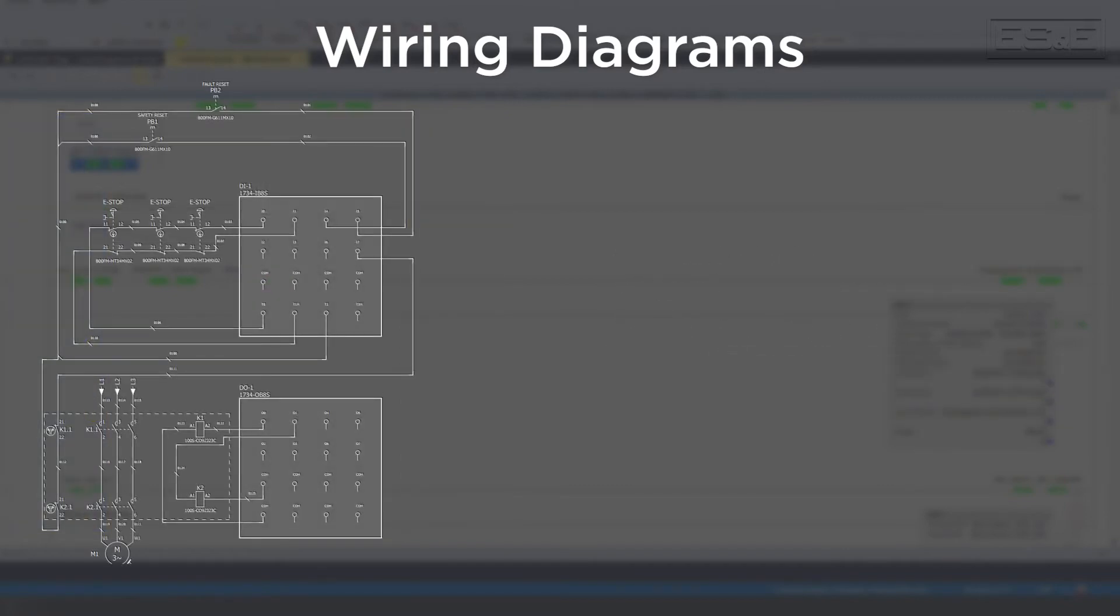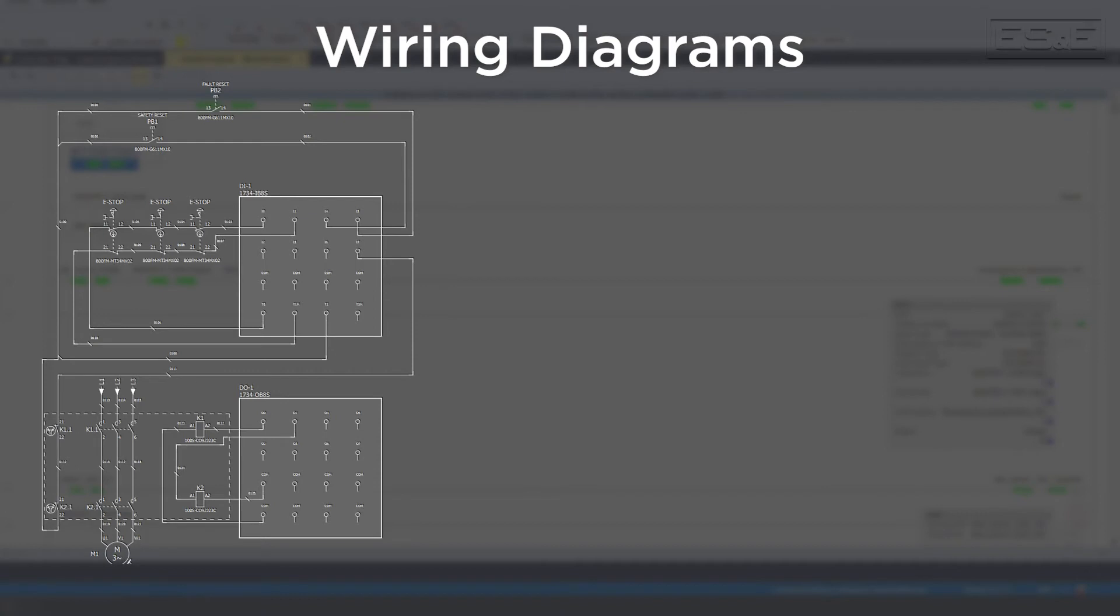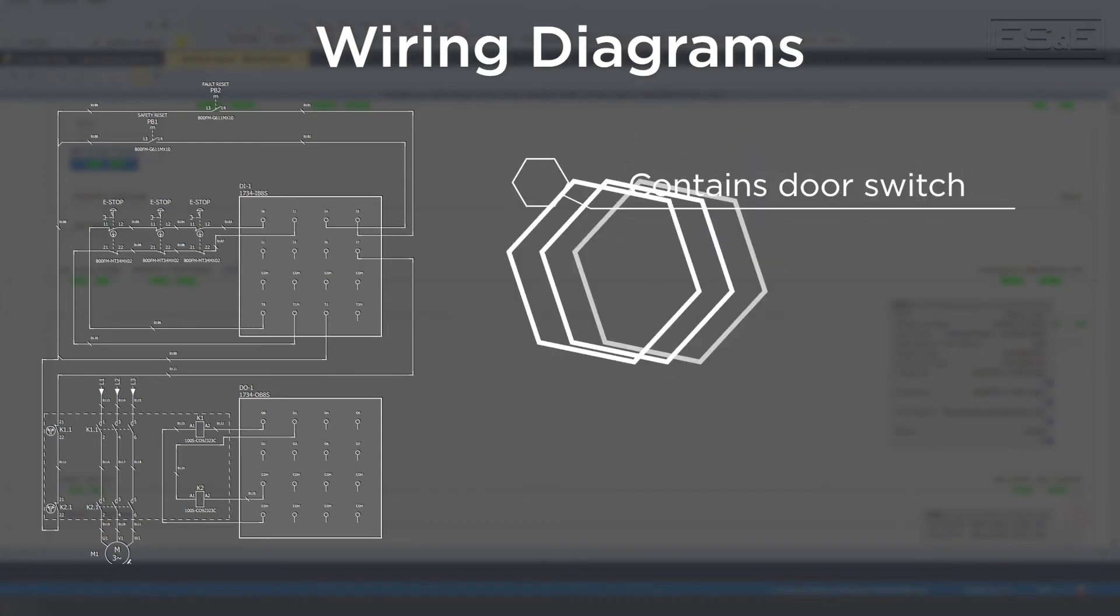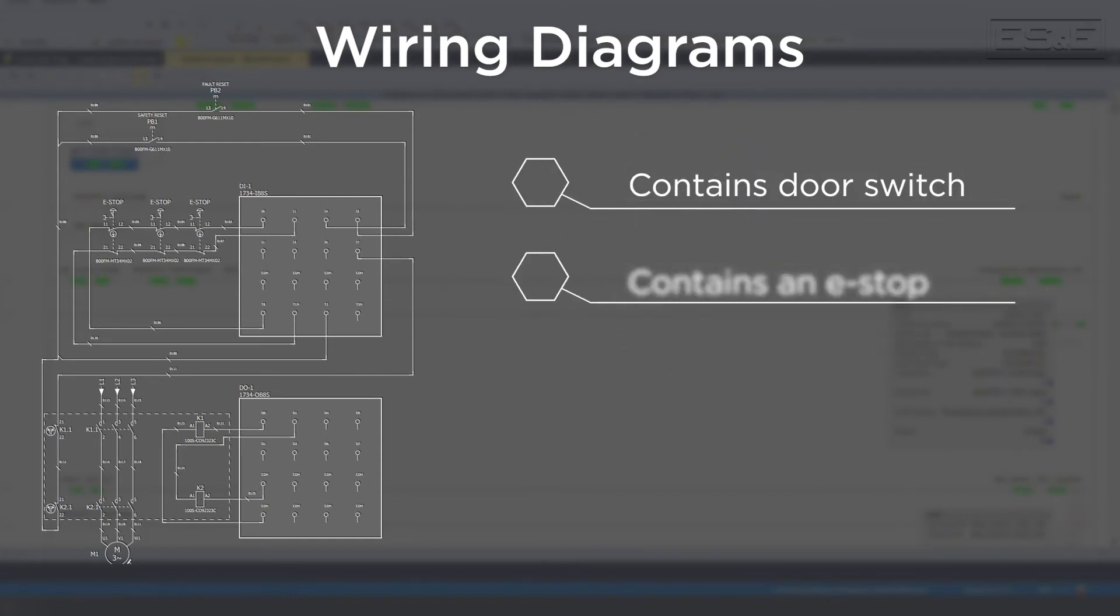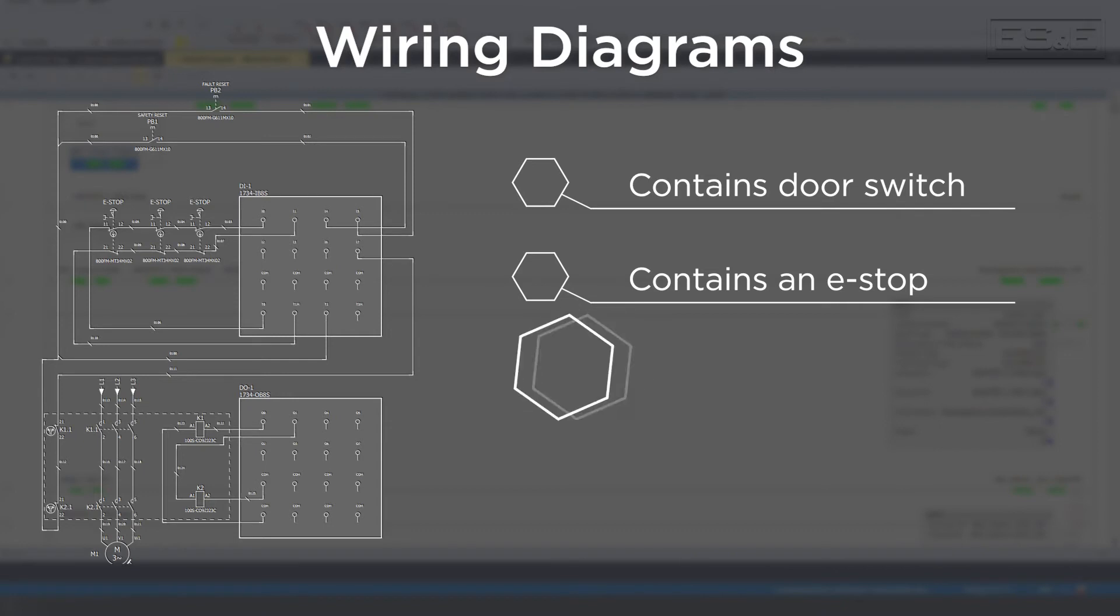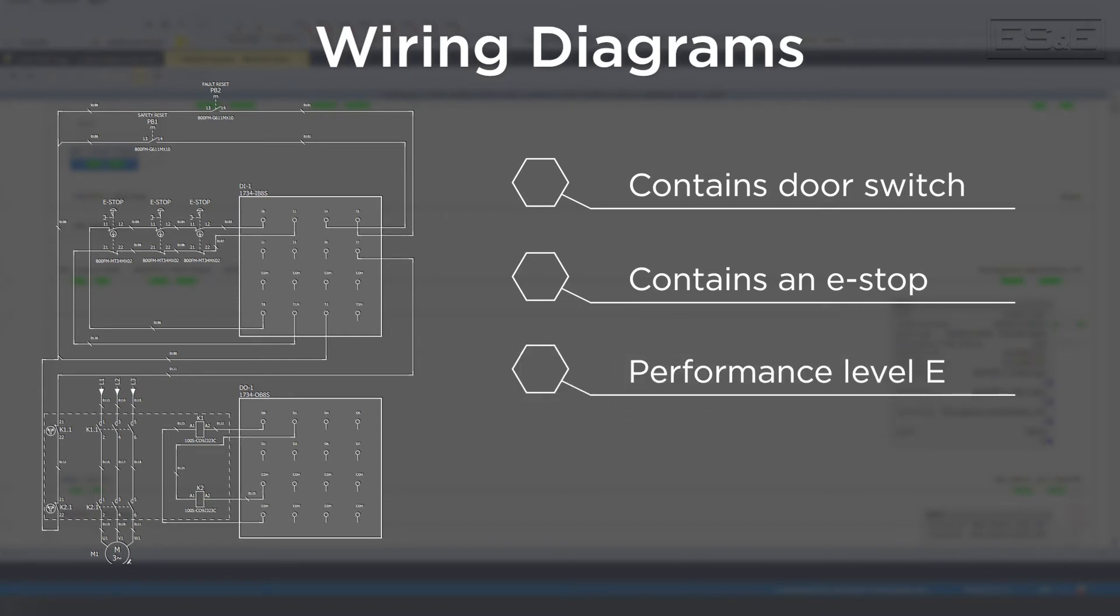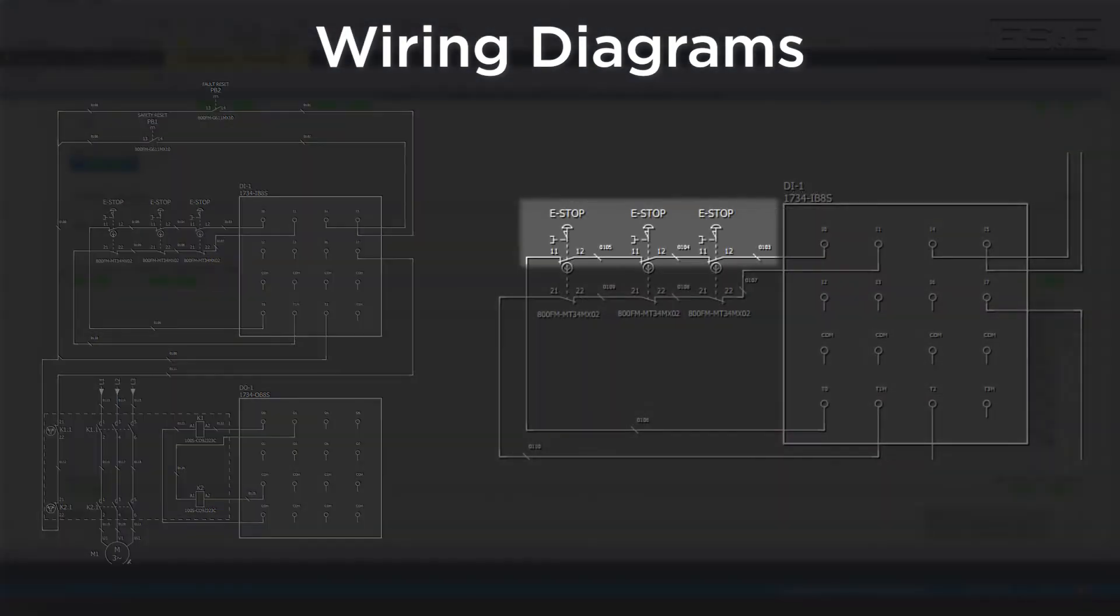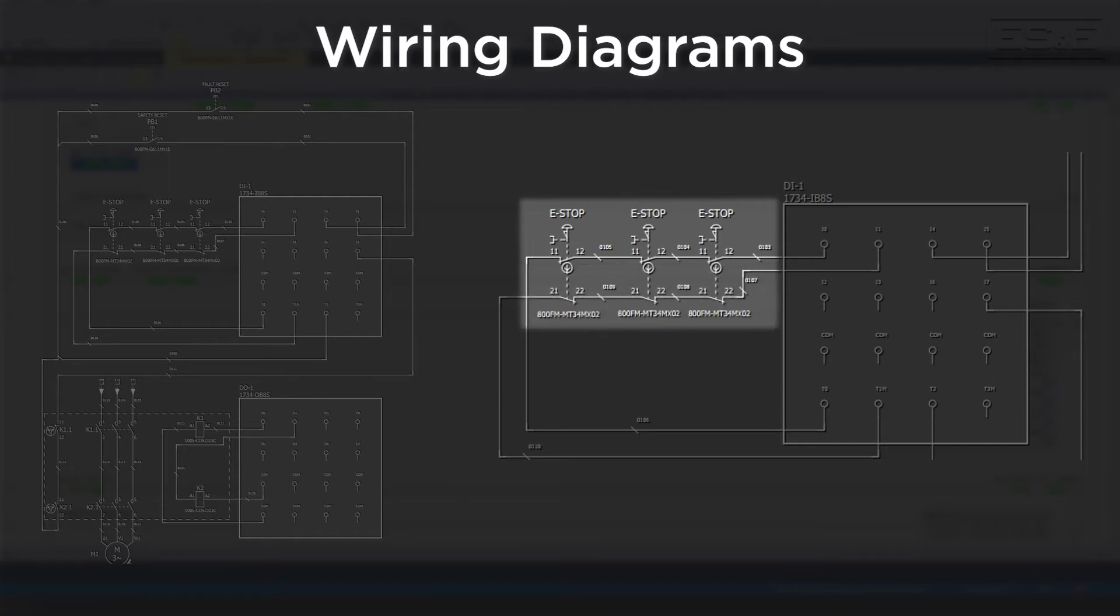Now, moving to a more complicated circuit that has a door switch along with an e-stop that is wired for a performance level E using dual circuits on both devices. Then we are going to enable another relay that can be used to supply power to a motor on the machine. On our safety relay, you will wire out of S11 into the door switch and then one contact on the e-stop and back into S12. Then you repeat the same for the second redundant circuit.